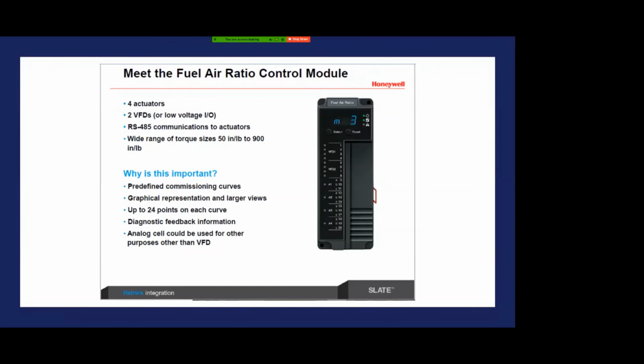That control link system has now all been integrated into this fuel air ratio control module. All of that functionality around controlling fuel and air to a tenth of a degree on a direct coupled actuator is in this module. You can configure this module through the display, establish your combustion curve, and do it all here. We have predefined commissioning curves and graphical representation to see the curve on our display. Each combustion curve can house up to 24 specific points along the curve. We also get diagnostic feedback from our actuators -- if there's a deviation or a comm loss to the actuators, we get that data too. This is another unique feature of the platform as a whole.